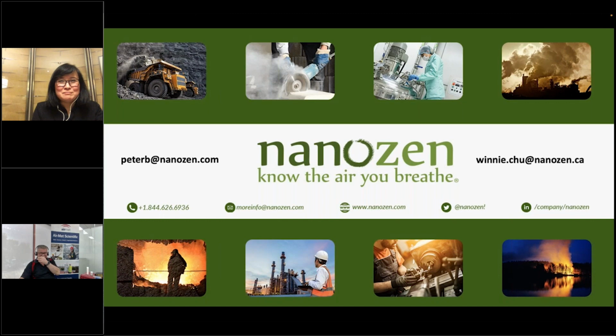Even I think I dropped the monitors a couple of times. They don't have to be kept upright. There's no orientation they have to be in. They are water resistant, like an IP62 or IP60, but they're not IP65. You can't immerse them in water, but they're pretty robust.